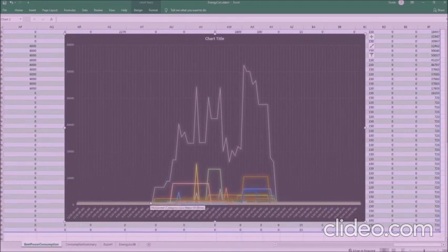This graph, for instance, shows a great proportionality between the power consumed and the occupants in the building. In the morning, as people are getting to the building, the power consumed increases, and in the afternoon, after lunch, it shows a great increase, which signifies the commencement of laboratories, and it starts decaying as students complete their labs.